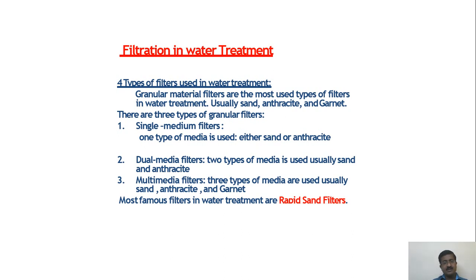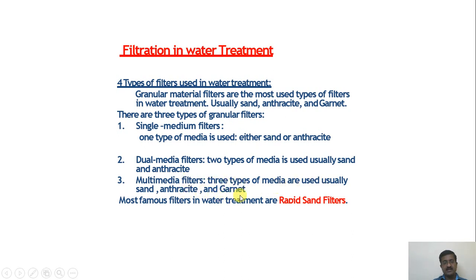Granular material filters are the most used type in water treatment, with sand, anthracite, and garnet being common materials. There are three types: single medium filters using either sand or anthracite; dual media filters using sand and anthracite; and multi-media filters using sand, anthracite, and garnet. The most common filters in water treatment are rapid sand filters.